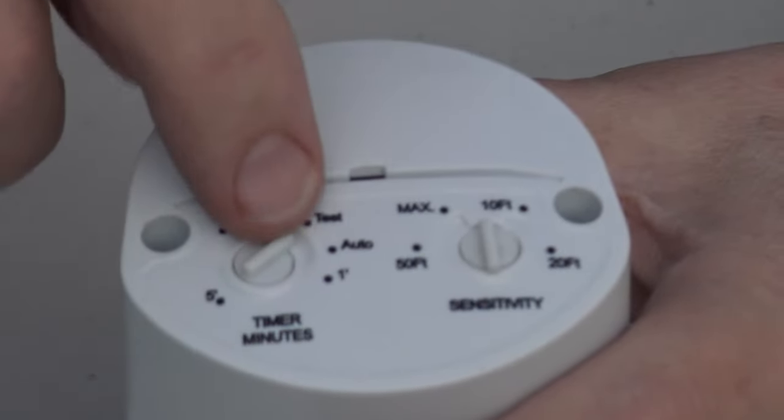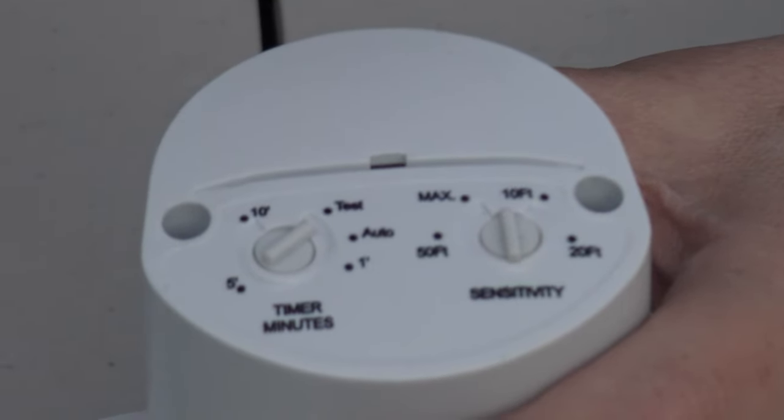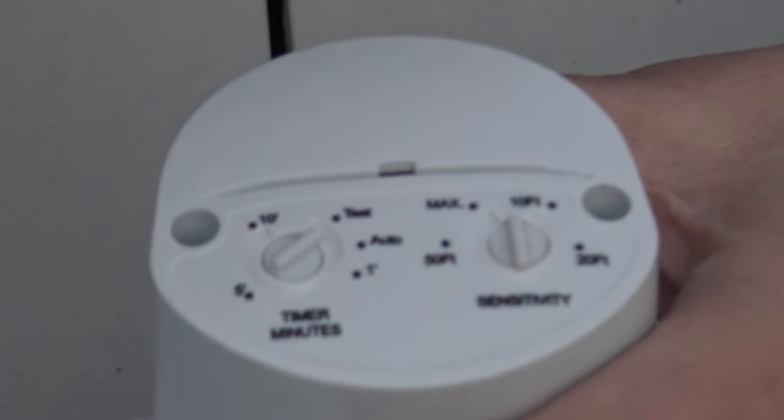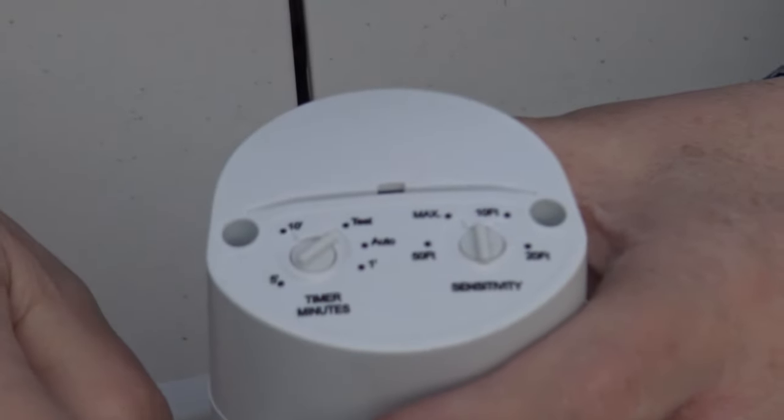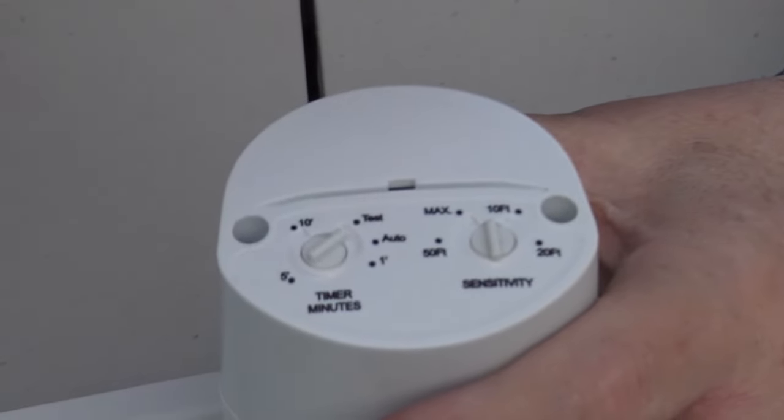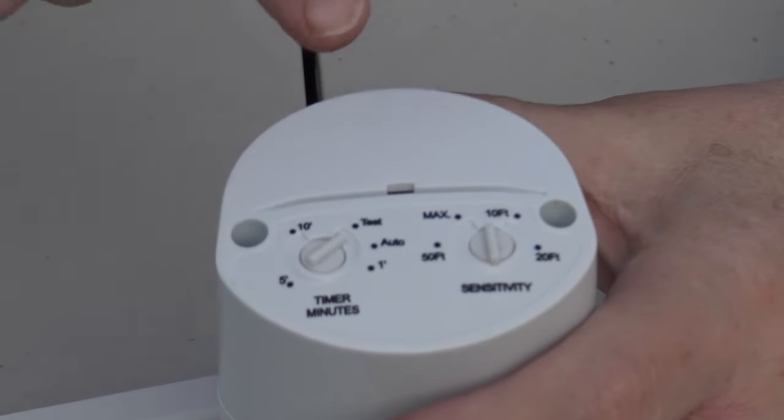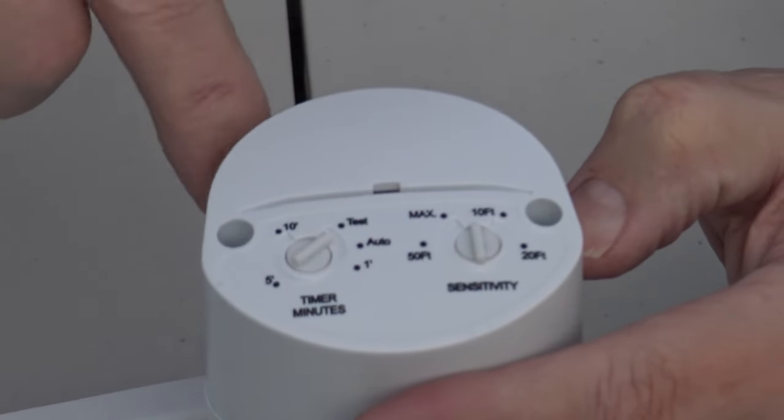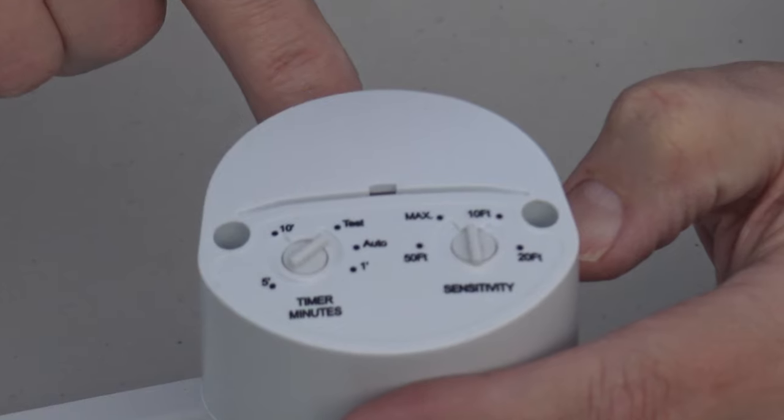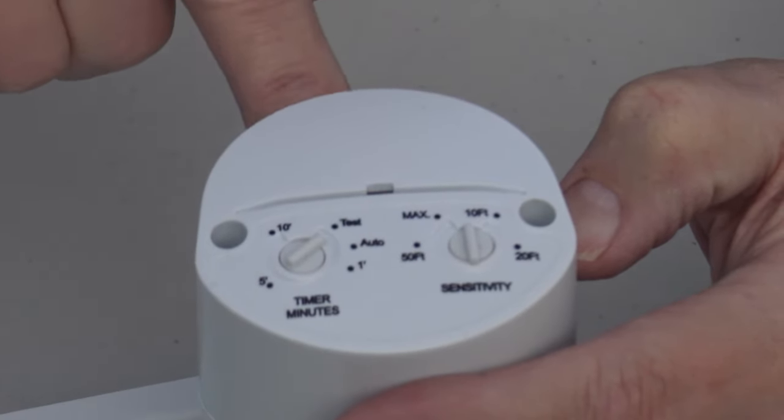When you set this to test and you turn on your power to the electrical box that controls the light, what the test mode allows you to do is essentially it disables the dusk to dawn control that's built into this. So normally during daylight hours...